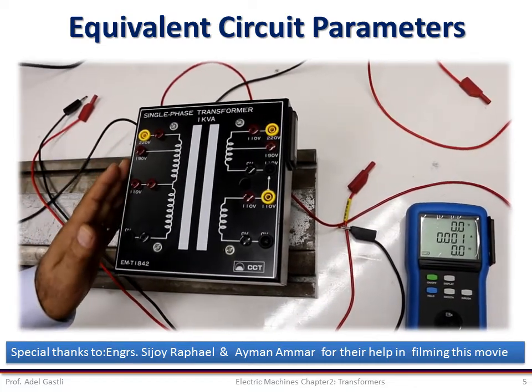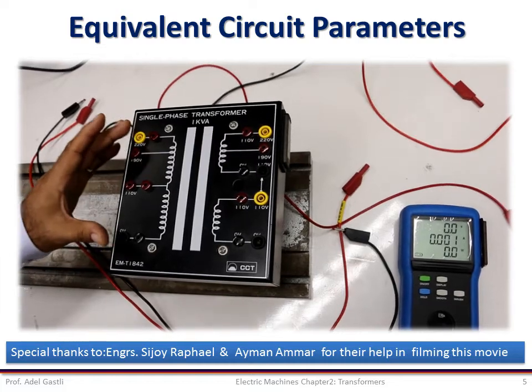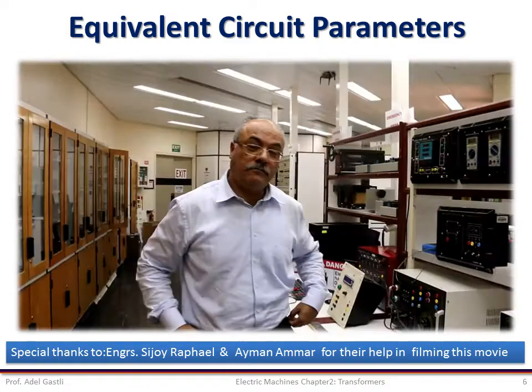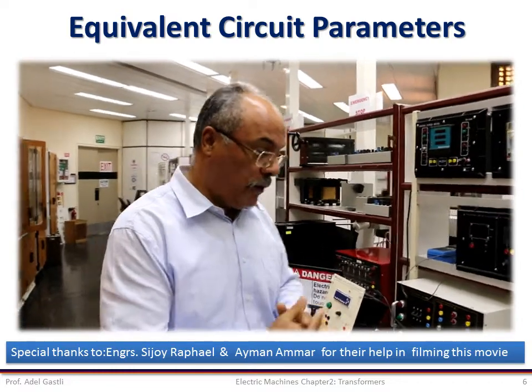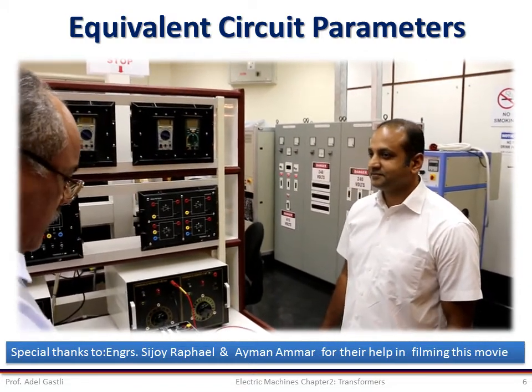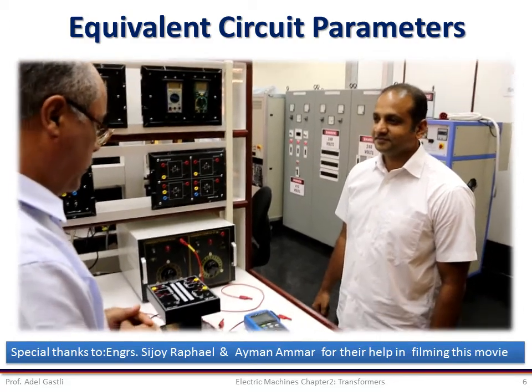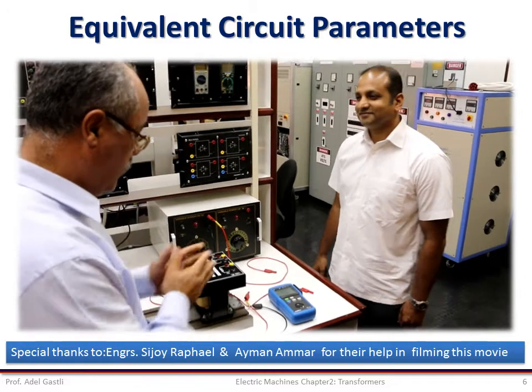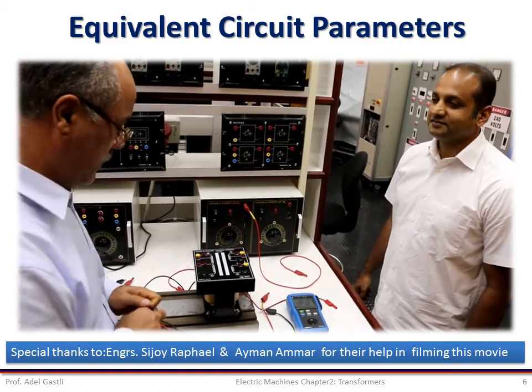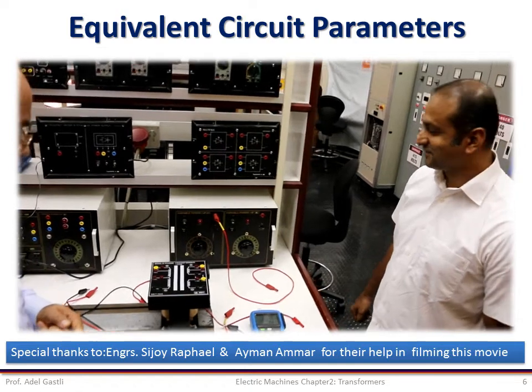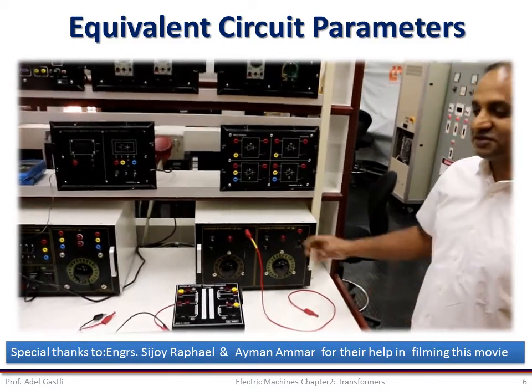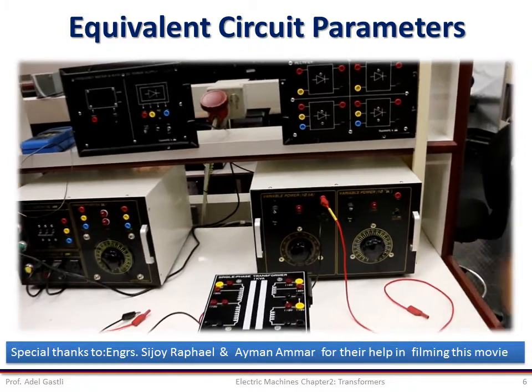The open circuit test, also called the no-load test, will be run at rated voltage while keeping the output open. We're going to show how to connect the primary to the source and place the ammeter, voltmeter, and wattmeter into the circuit so that we can measure the open circuit voltage, current, and power. We're going to use one single device that can act as ammeter, voltmeter, and wattmeter at the same time. This is the power supply — a variable power supply — so we have to adjust it to the rated voltage of the single phase transformer for the open circuit test.